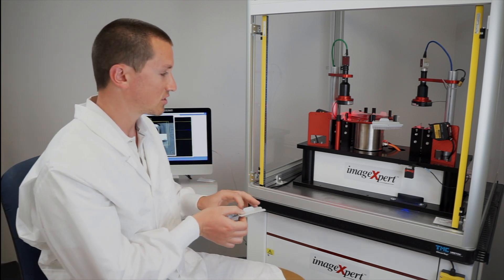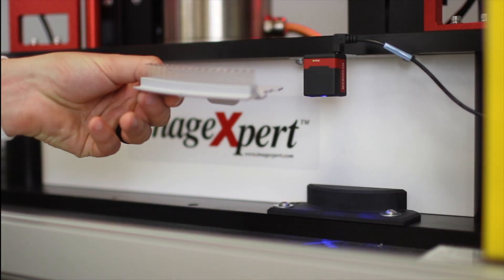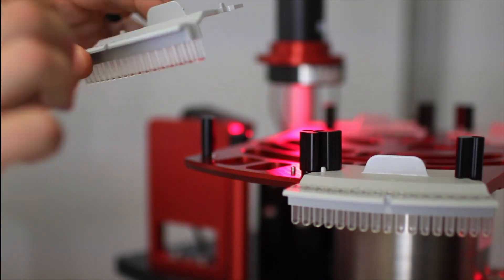To begin the inspection, the barcode on the back of the cuvette is scanned with the barcode scanner to help trace the part throughout the entire production line.